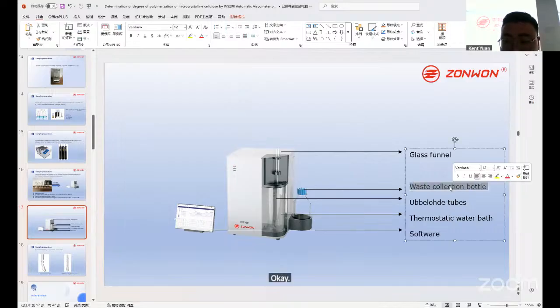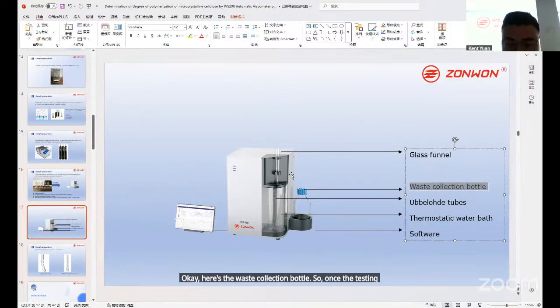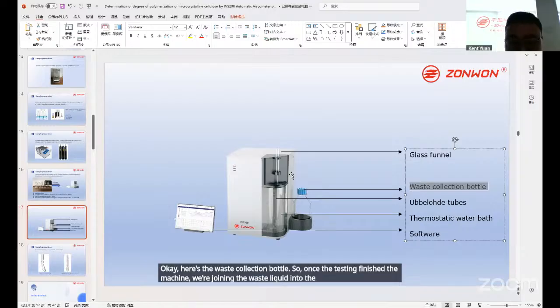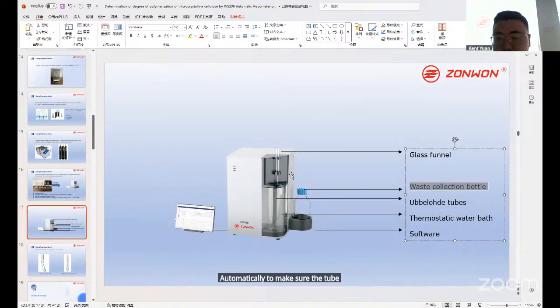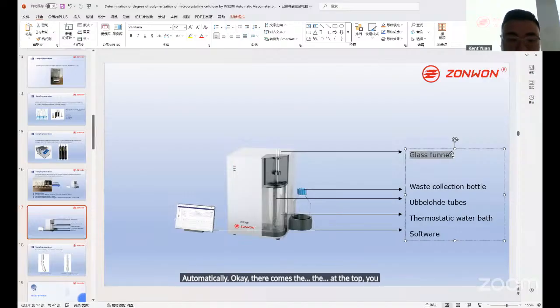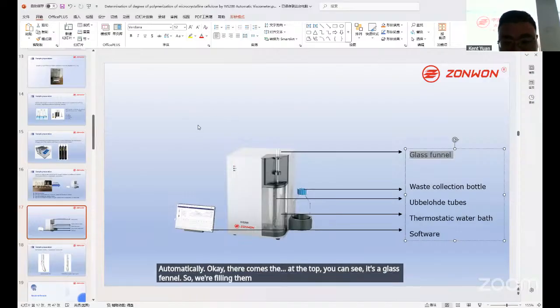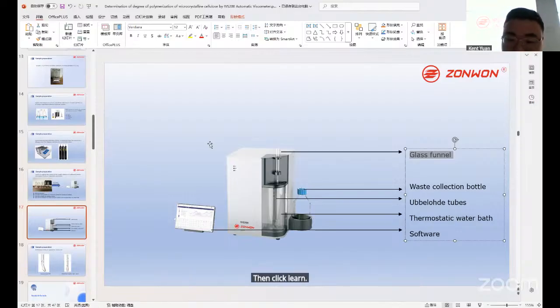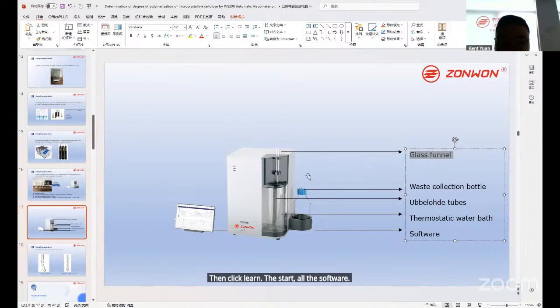Okay, here is the waste collection bottle. Once the testing is finished, the machine will drain the waste liquid into the bottle automatically to make sure the tube is empty. Then you fill in the wash agent into the tube for washing. It is dried automatically. Then at the top, you can see a glass funnel. We fill the liquid or sample through the glass funnel into the Ubbelohde tube, then click start on the software. It will do the testing automatically.